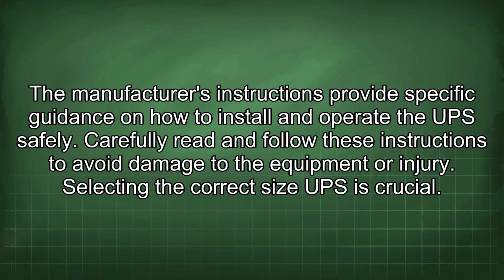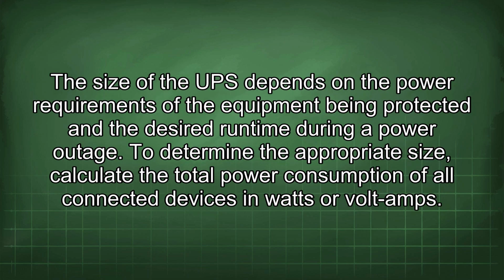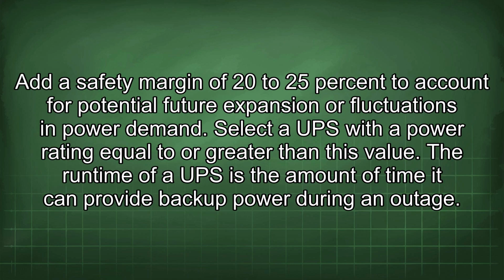Selecting the correct size UPS is crucial. The size of the UPS depends on the power requirements of the equipment being protected and the desired runtime during a power outage. To determine the appropriate size, calculate the total power consumption of all connected devices in watts or volt amps. Add a safety margin of 20 to 25% to account for potential future expansion or fluctuations in power demand. Select a UPS with a power rating equal to or greater than this value.